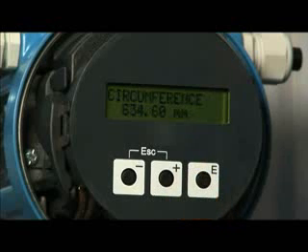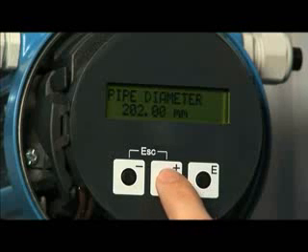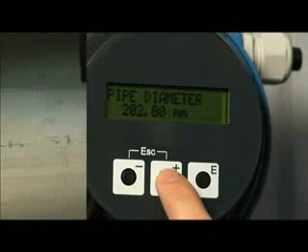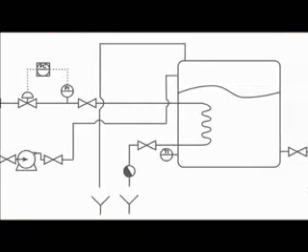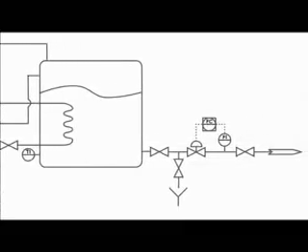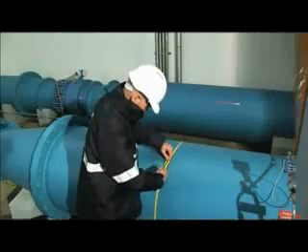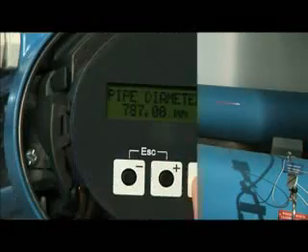You now have the choice of entering either the outer pipe circumference or outer pipe diameter. After entering one of the values, the other value is automatically calculated. The outer pipe diameter can often be found printed on the pipe along with the pipe wall thickness, or in a PID control drawing of the system, or using a piping reference book. If the pipe diameter cannot be found, we suggest measuring the circumference of the pipe and entering that value.